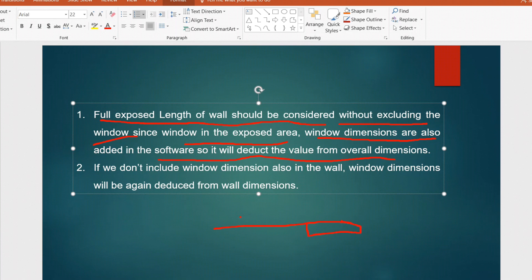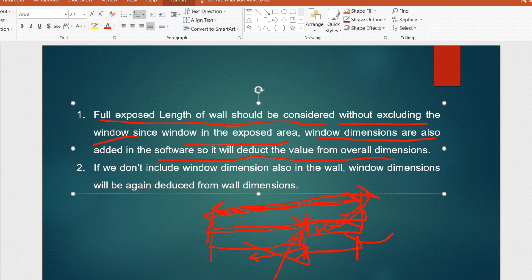Since the window is in the exposure area and window dimensions are also added separately in the software, it will deduct the window value from the overall dimension automatically. In our case the total length is 5.5 feet and the window is 2.2 feet — we must enter the full 5.5 feet. If by mistake you provide only the solid wall length and then add the window dimension separately, the software will double-deduct. You must provide the full exposure length; if there is a window or door, enter that area separately but do not deduct it from the wall length.